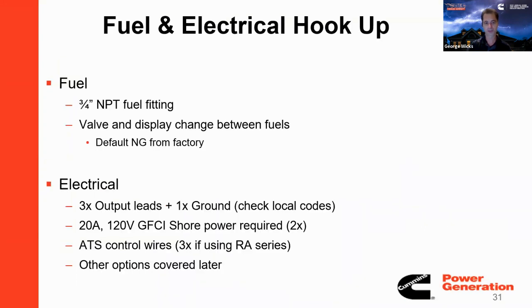So the 3/4 inch fitting we mentioned is pretty basic for a 20 kilowatt generator. And the electrical output's pretty simple, with 3 output leads and your grounds. That's common for any 20 kW. A 20 amp 120 volt circuit from the house is required, and you're only talking 3 low voltage wires from the generator to the transfer switch. That's it. There are other options available that would require more wiring, but that is the basic setup.